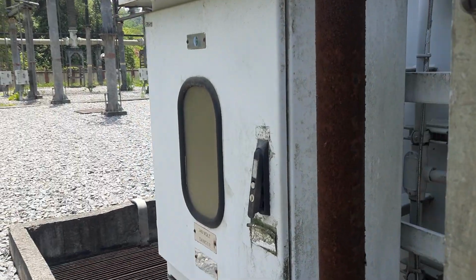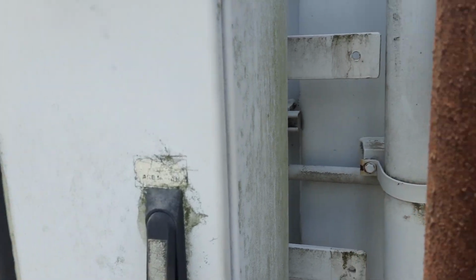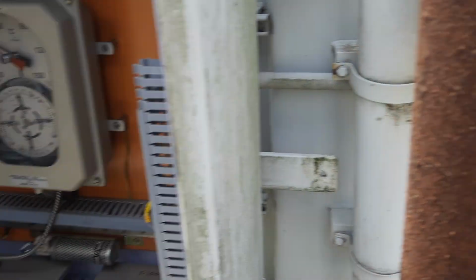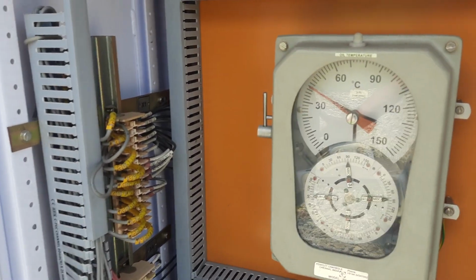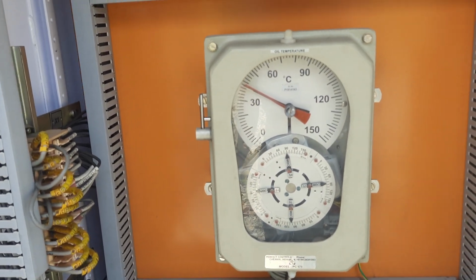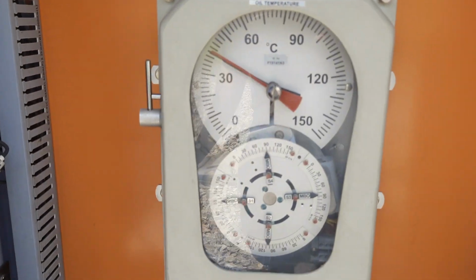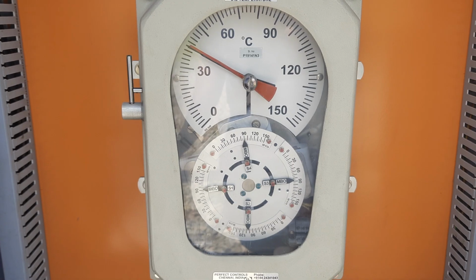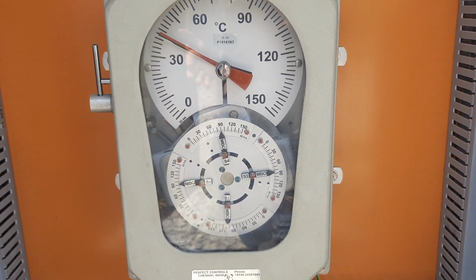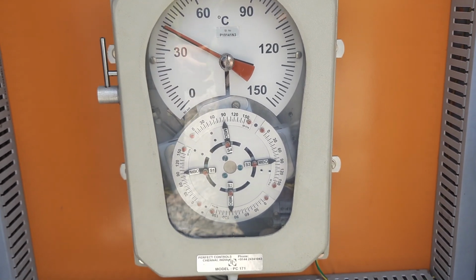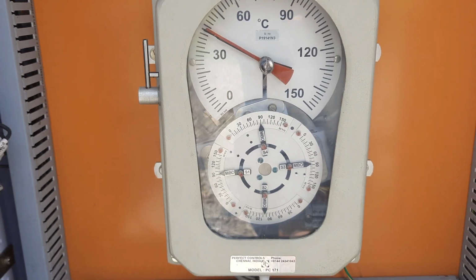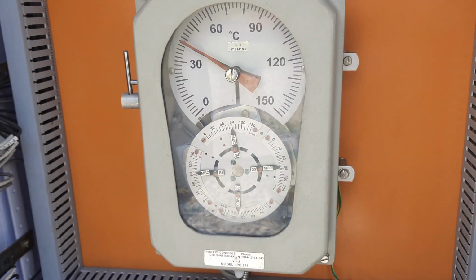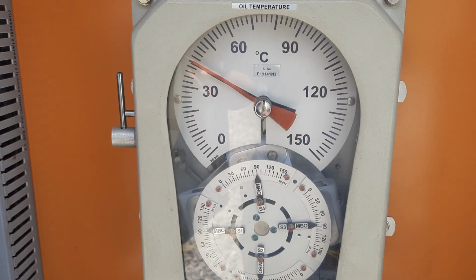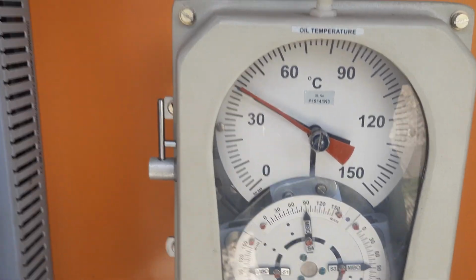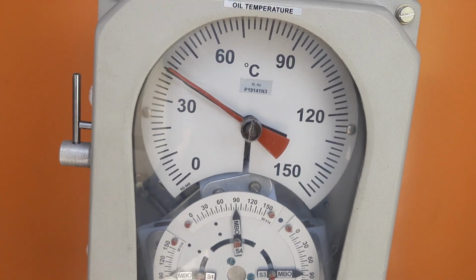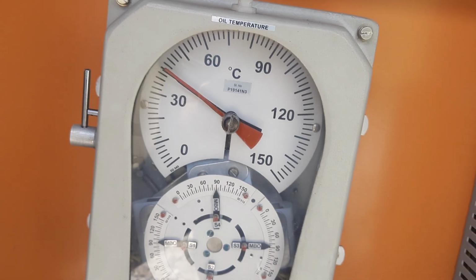So there is a marshalling box also here. If you open it, inside you will see the oil temperature indicator. You can see the range from 0 to 150 degrees Celsius, and the settings have been provided for both alarm and trip. The alarm setting is 85 degrees Celsius, and the trip setting is 95.